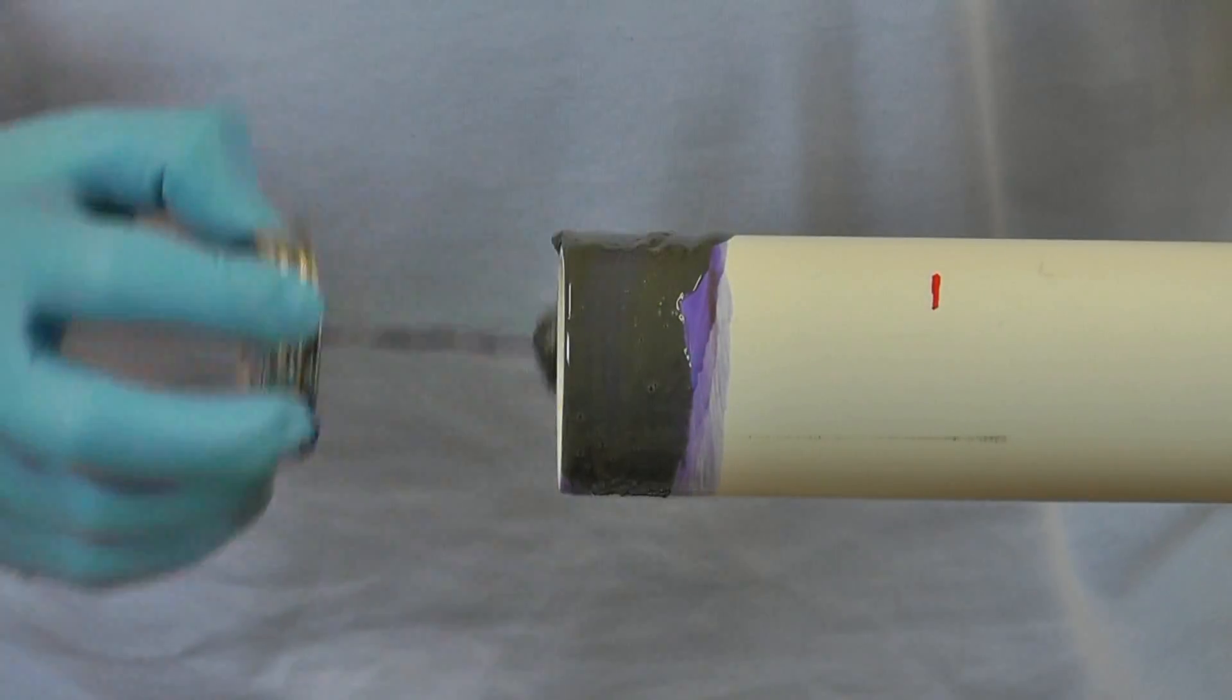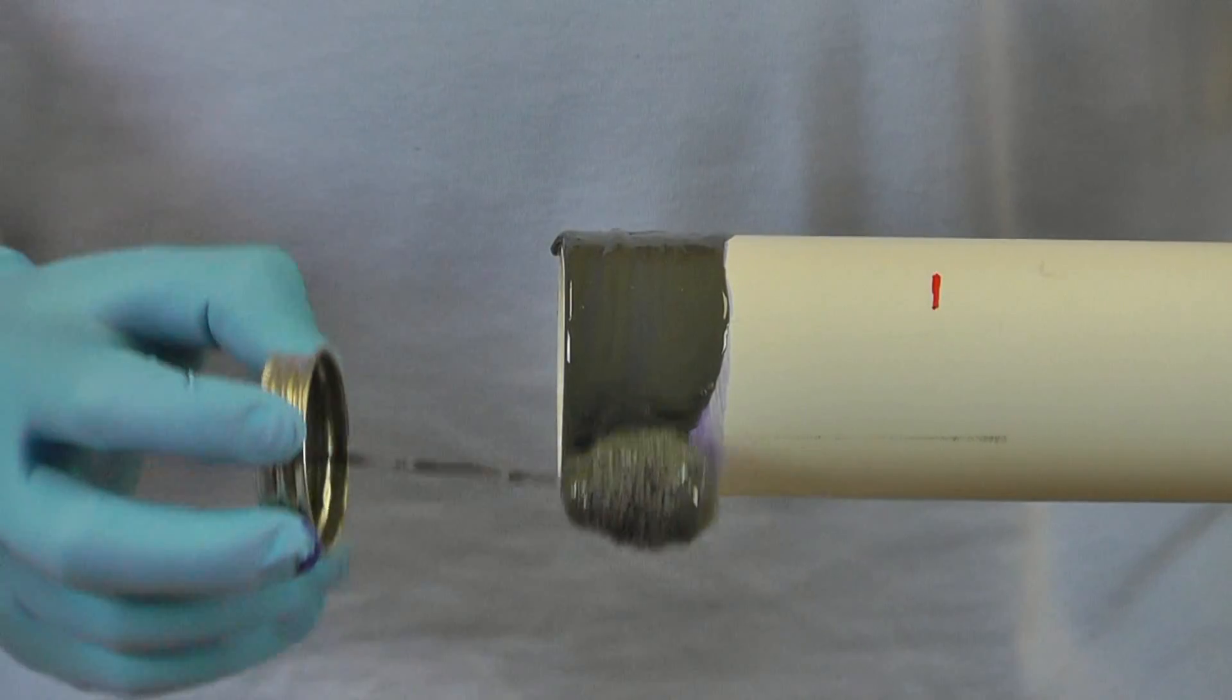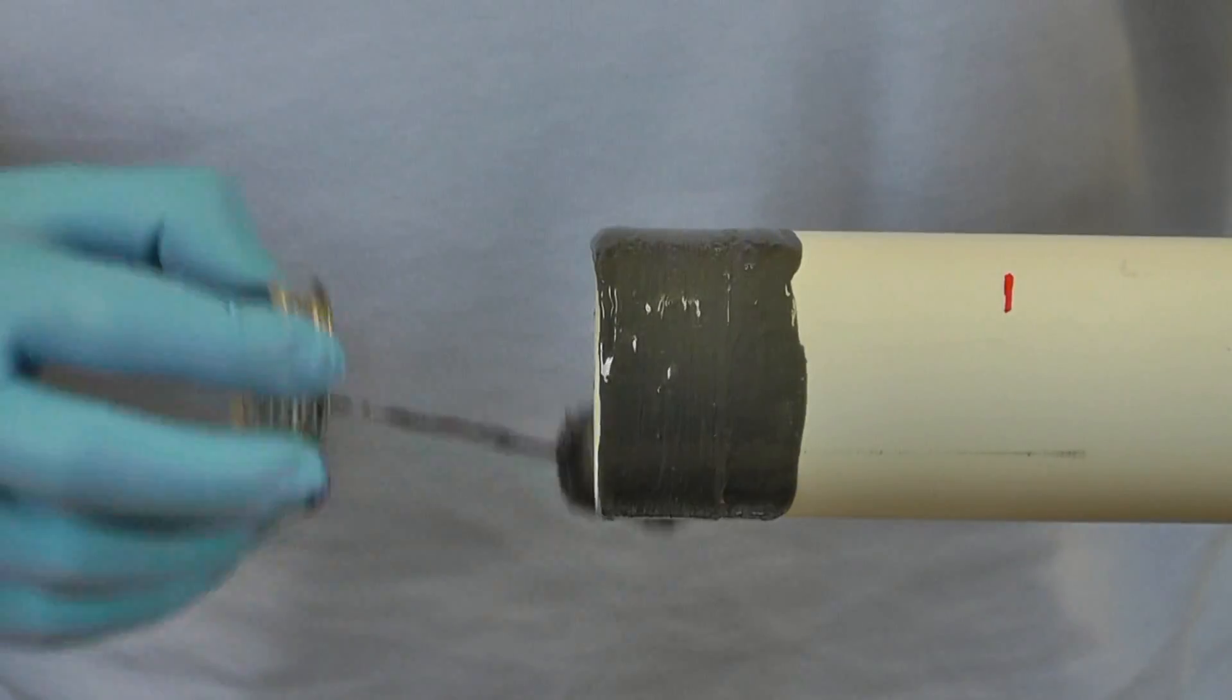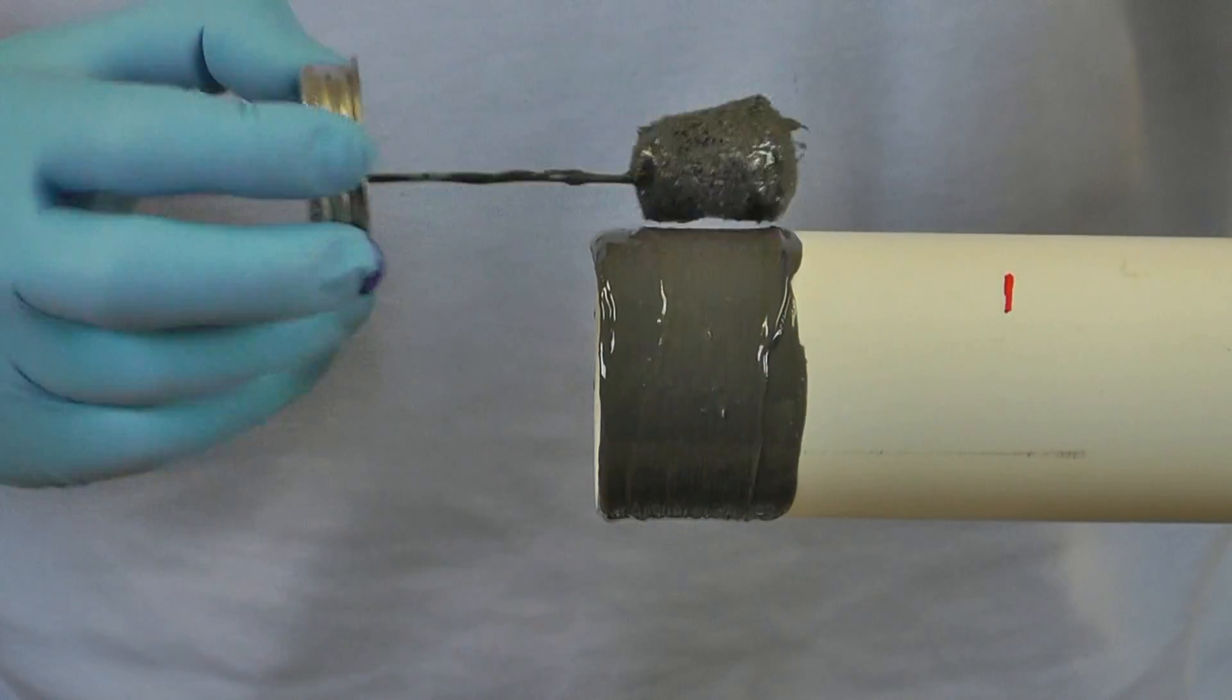Without delay and while the primer is still wet, apply the cement to the pipe, then to the fitting, and again to the pipe. Use a circular motion and apply a thick even coat to the pipe with a thinner even coat inside the fitting. Again, work quickly but do not allow cement to puddle inside the socket or run down the pipe.